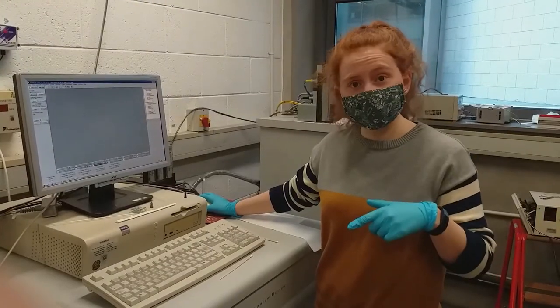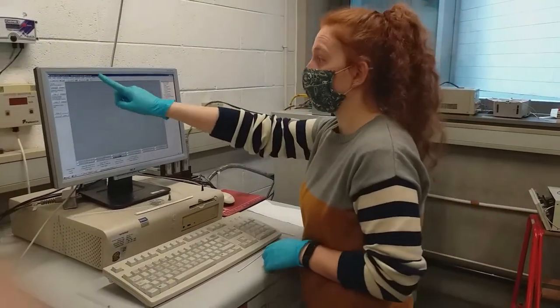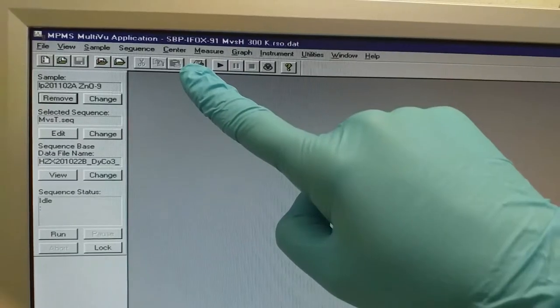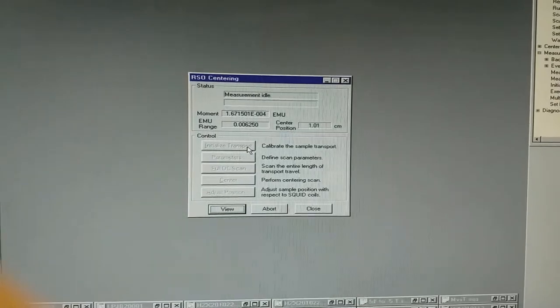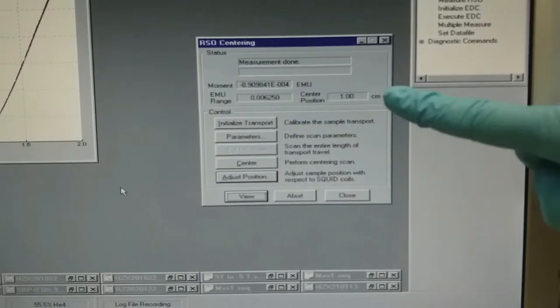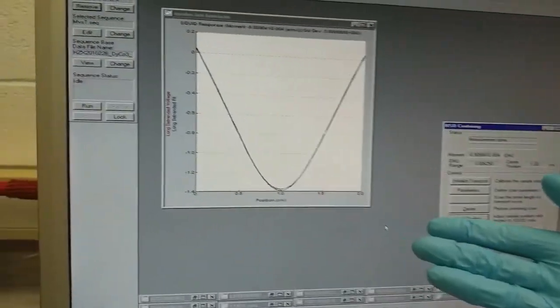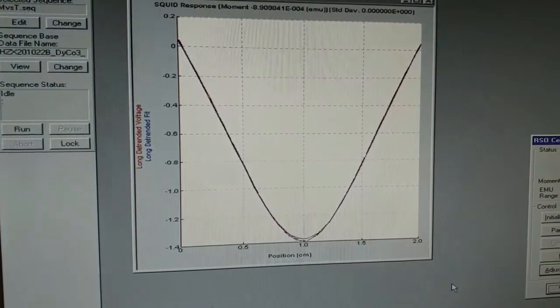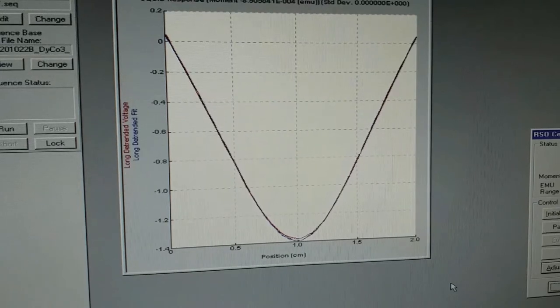Now I need to center the sample to make sure that it's at the center of the SQUID pickup coils, and I do this by clicking the center button here. I click initialize transport to lower the sample down, and then in the parameters window I can define the scan length. I have set the length to 2cm so I want the center to be at 1cm. I adjust the position until I get this. Here you can see the voltage response curve and its fit. At the minimum here the sample is exactly centered between the coils, so you can see that this is ready to go.